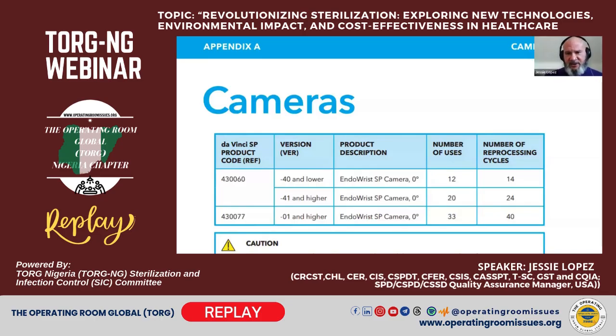It is expired now. We utilize the higher version of the camera here, which gives us 33 usages with 40 reprocessing cycles. And that may seem like a lot, but here in my facility, we do anywhere from 7 to 10 robotic surgeries per day, and we only have about 3 of these cameras. So think about that usage. If you divide the 3 cameras into the 10 surgeries, you get 3 usages a day. You only got 11 days of usage.